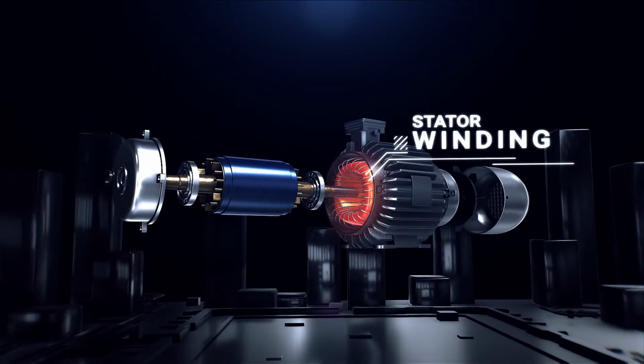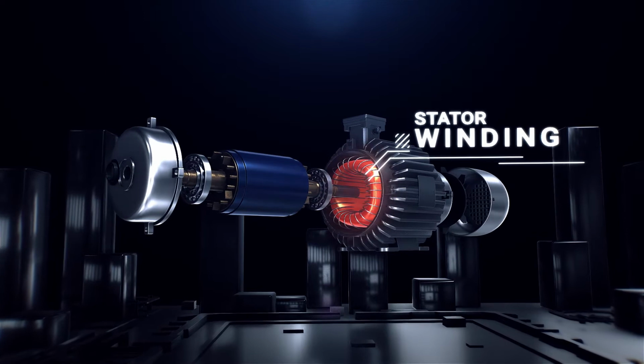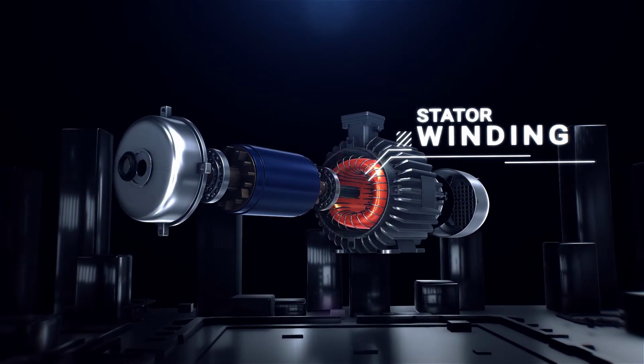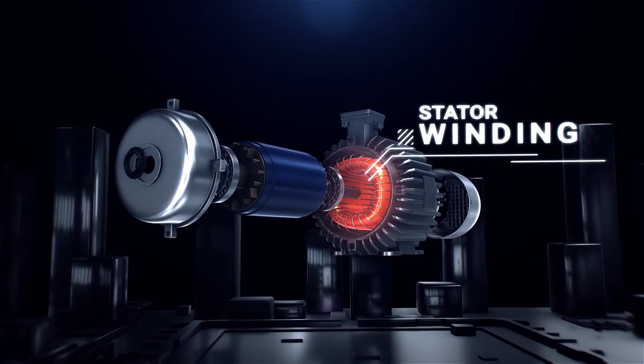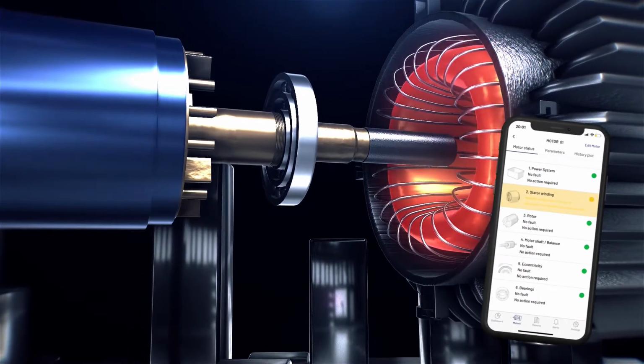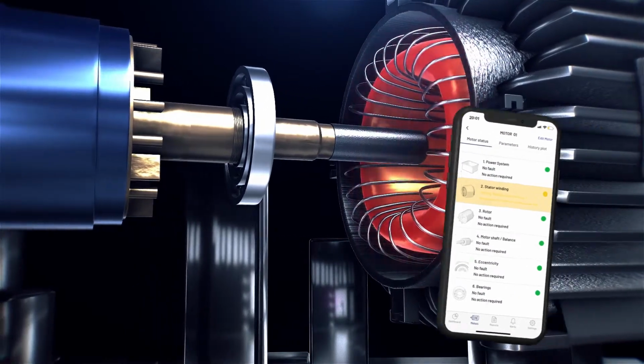Problems with the stator winding. Electrical failure. Due to insulation problems between the coils, a short circuit can occur in one of the motor phases. This increases the current and creates an imbalance between the phases.